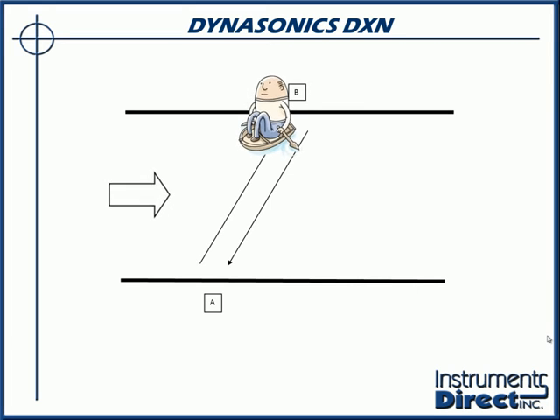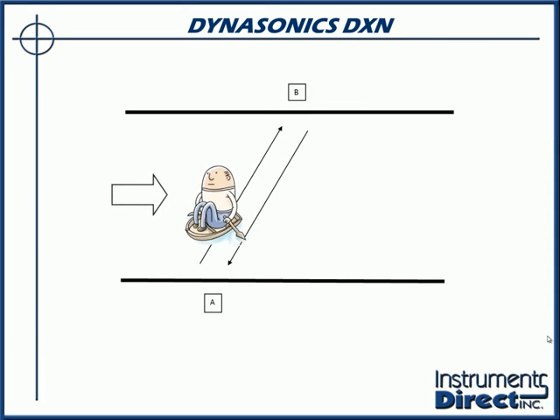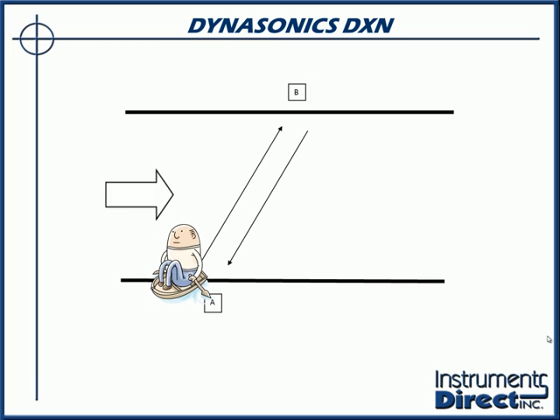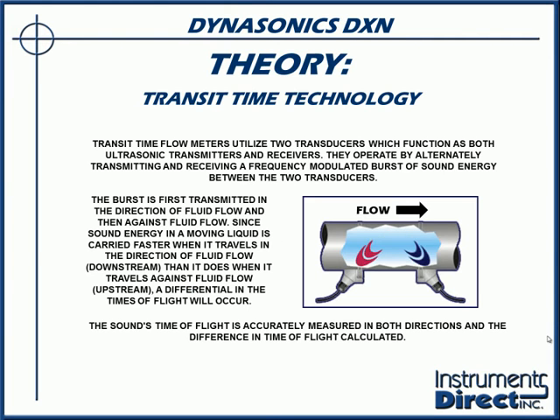So with the current, he goes across fast. When he comes back, he goes against the current. There's a differential. The faster the flow rate, the greater the differential. That's the coefficient we use to derive how fast the river is flowing. Now, if we were to apply the same theory using a pipe, I've got a bird's eye view right here looking down across the top of a pipe, and instead of across the river, I'm ricocheting off the back wall. So, sensor on the left, I send a sound beam, blast across the pipe, and bounce off the back wall to the sensor downstream.